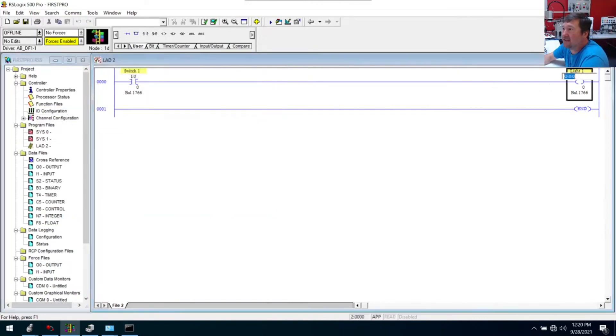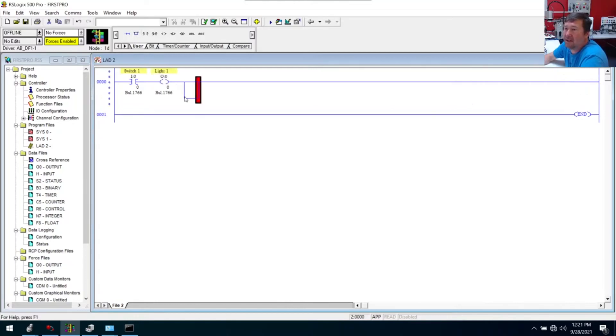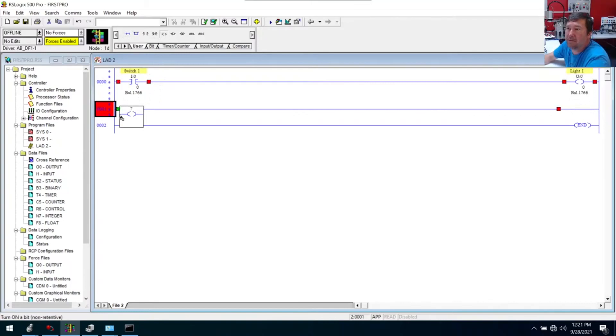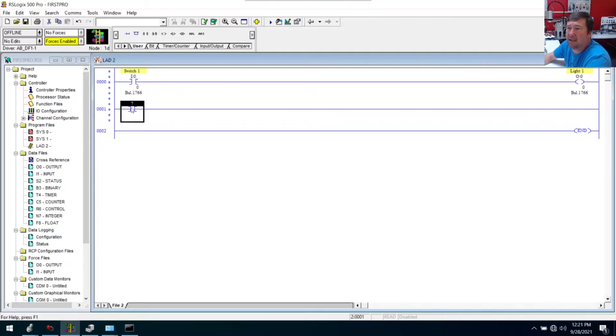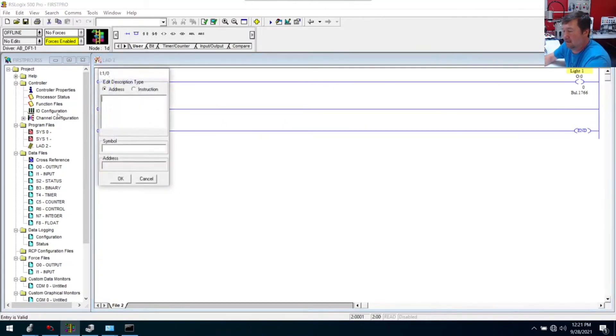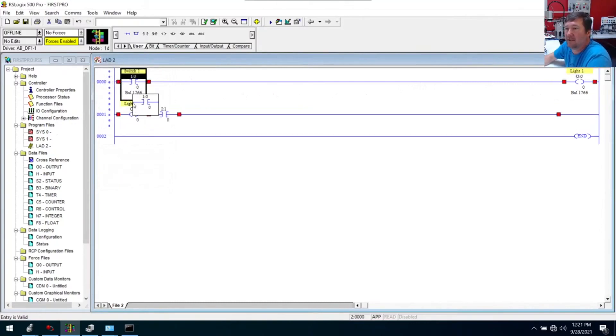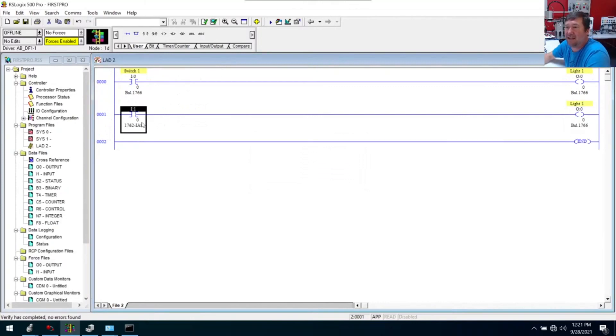I just put that in slot one. You notice this is zero right here, this is O:0/0. That means this is the output, it's in zero which is the base of the PLC, and it's output zero. Let me make another rung. Let's add another rung down and we're going to put an output in. We want an input. Now let's start typing I:, but this time I'm going to put one and enter. Copy then paste this down. Now I'm going to hit the verify button. This one says 1762 IA8, so that tells me what module this input is connected to.